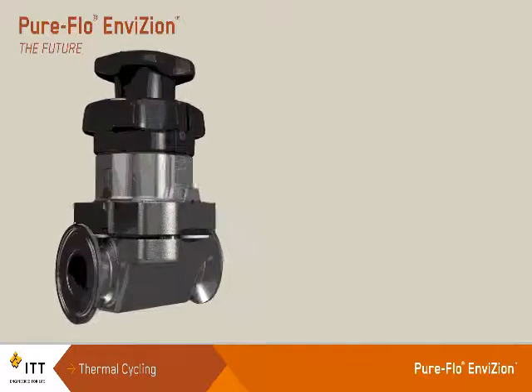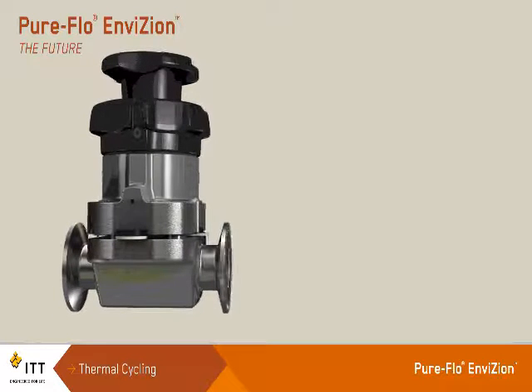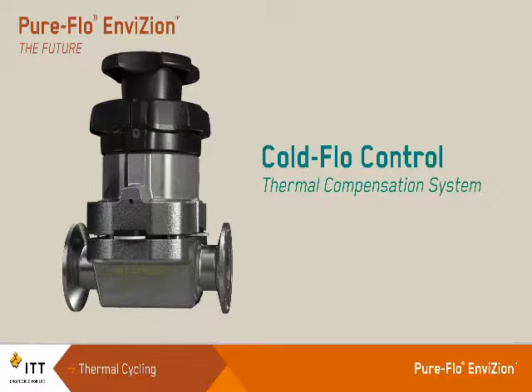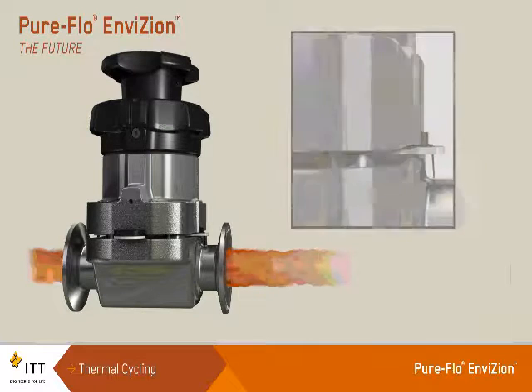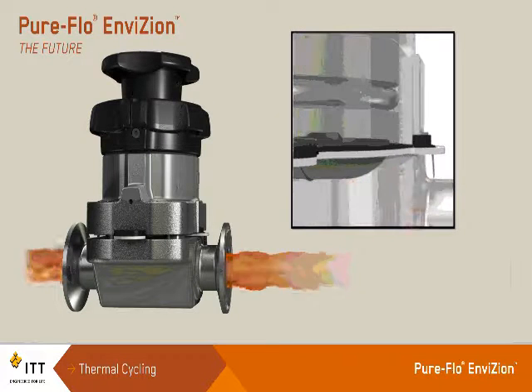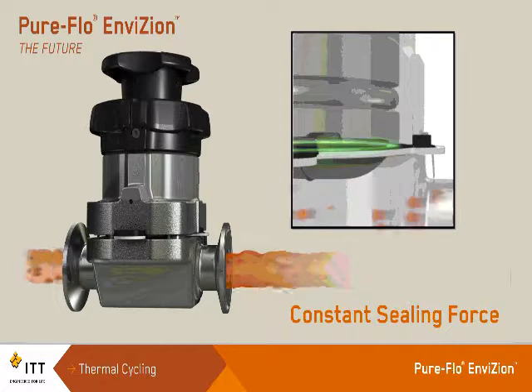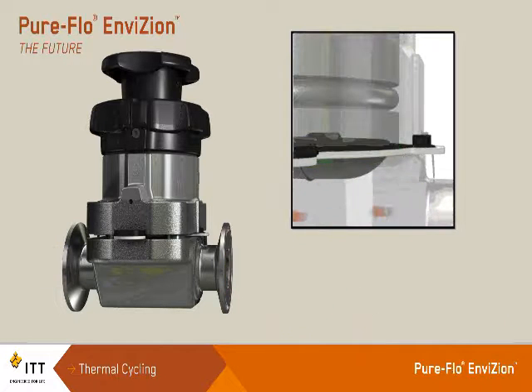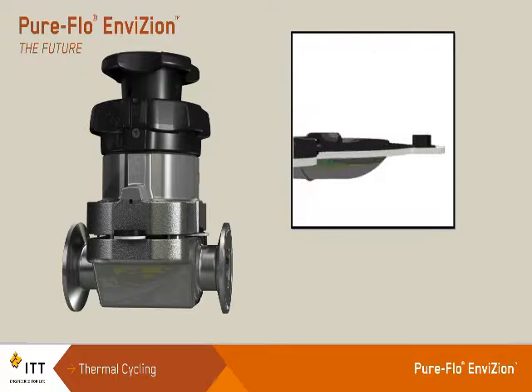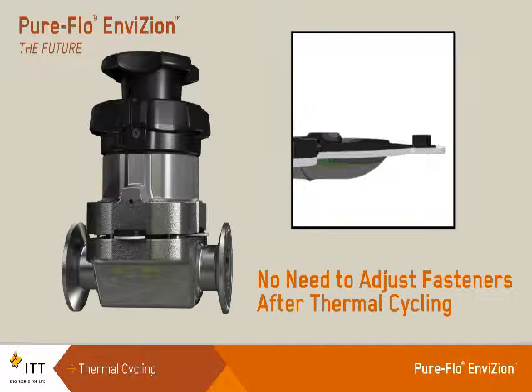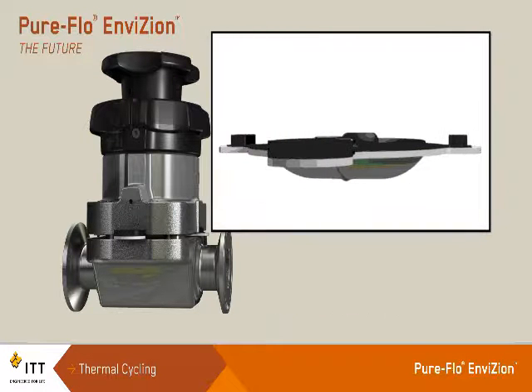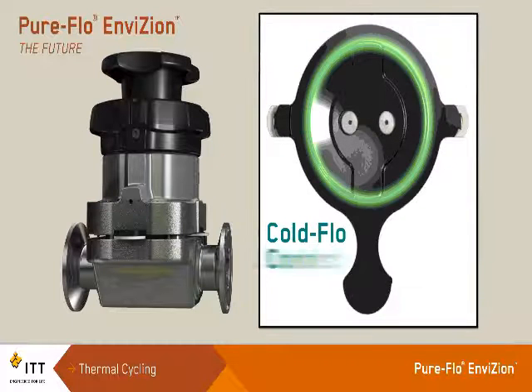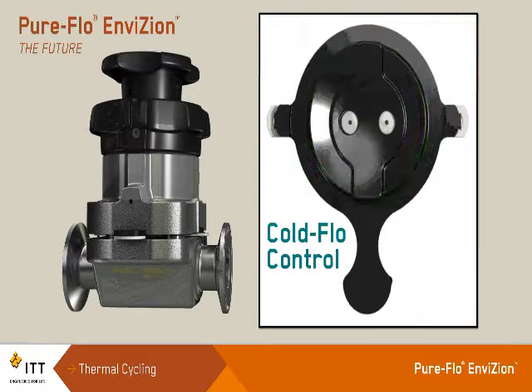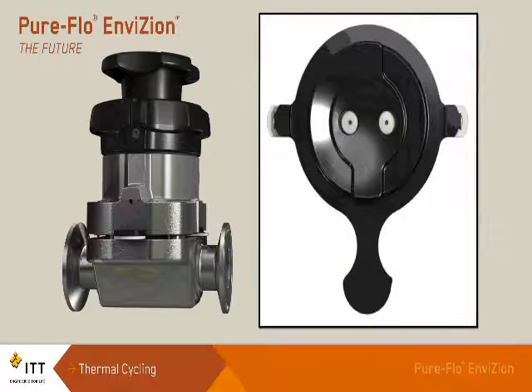The Pure-Flo EnviZion eliminates the effects of thermal cycling with ITT's cold flow control thermal compensation system. Inside the topworks, the cold flow control provides a constant sealing force against the valve body and diaphragm, maintaining a seal over varying operating conditions and eliminating the need to adjust fasteners after thermal cycling. This innovative technology assures body seal reliability across extreme thermal cycling conditions, reducing maintenance hours, commissioning time, and the potential for system contamination.